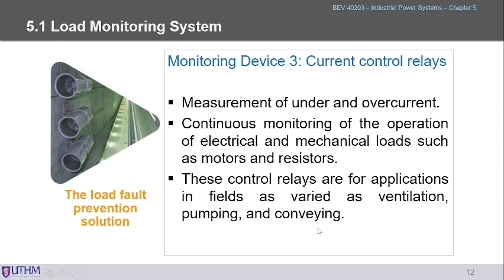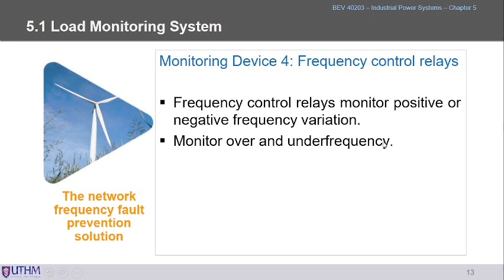For the network frequency, now we're talking about network frequency prevention solutions, we can use frequency control relays. These relays monitor the positive and negative frequency variations, that means the upper and lower levels. For example, if we have 50 hertz, the upper tolerance is plus 1% and the lower side is minus 1%. We can monitor whether we have over-frequency or under-frequency conditions.